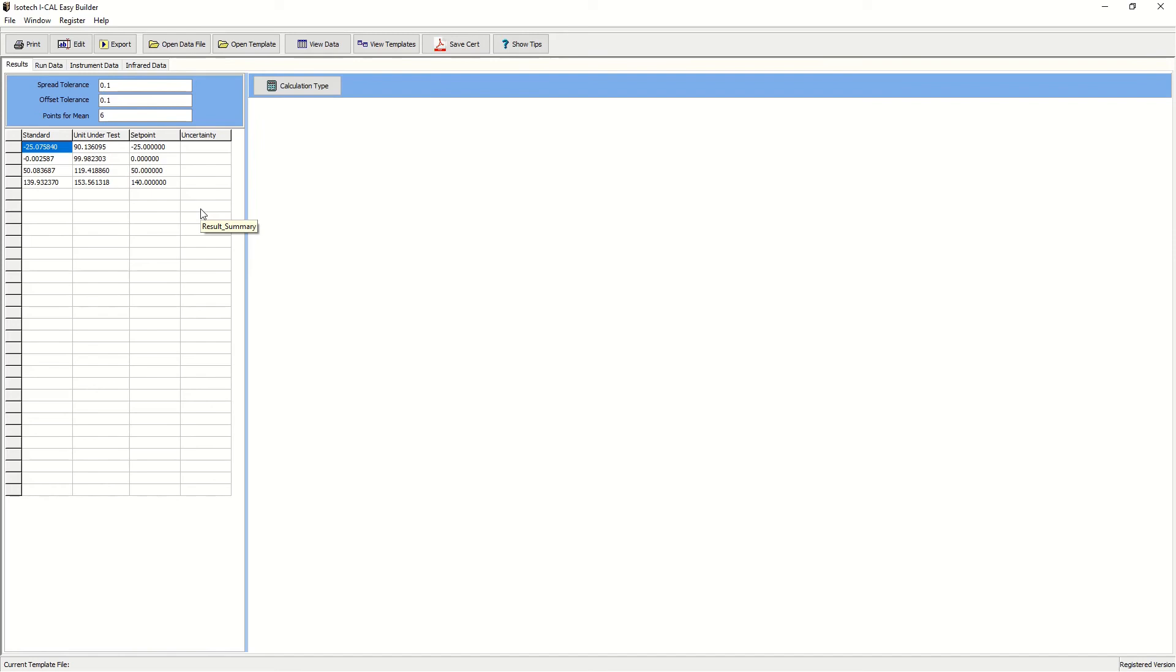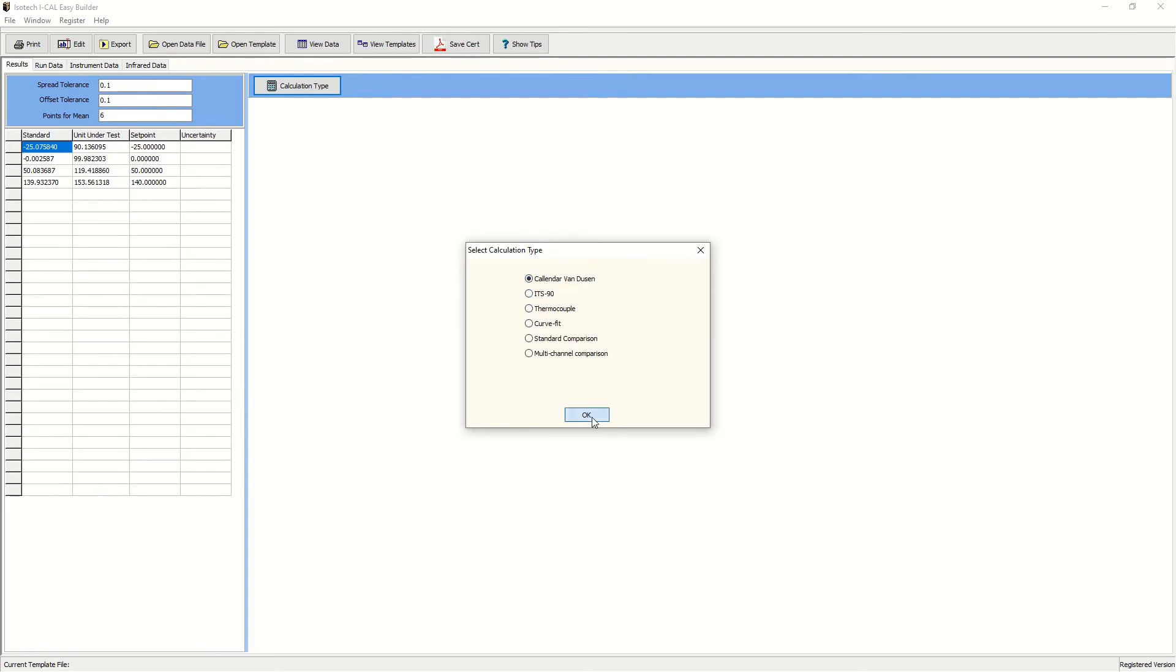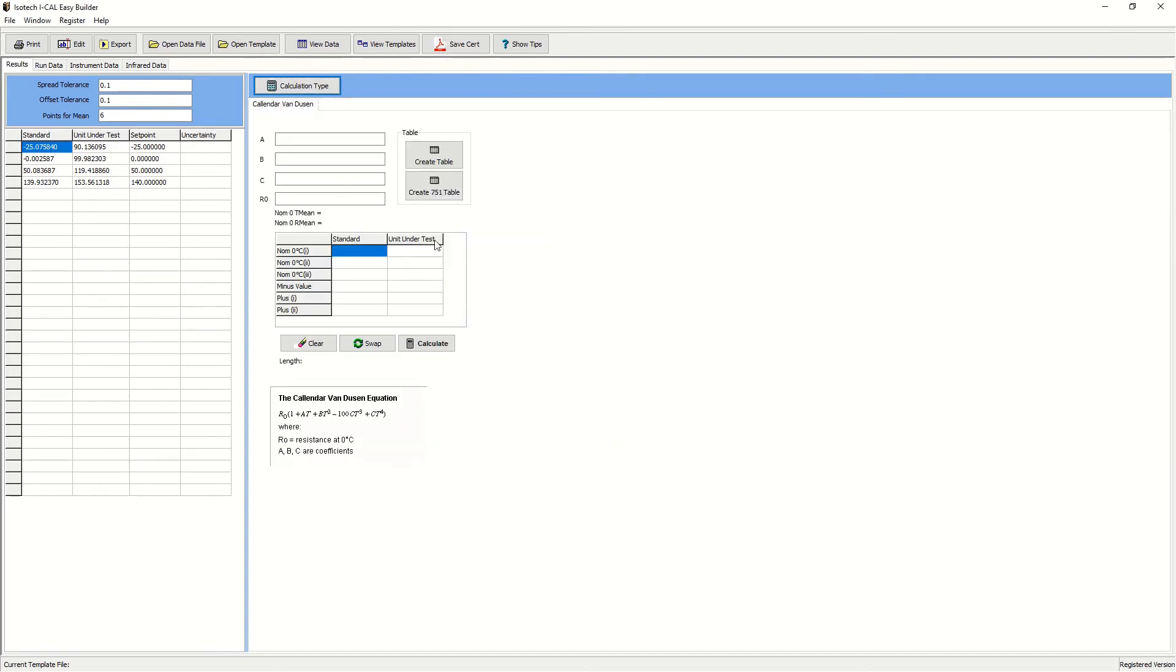Now this is the raw data and we can perform calculations to calibrate these. And we have options in this software for Callendar-Van Dusen, ITS-90, thermocouple correction coefficients and regression equations.